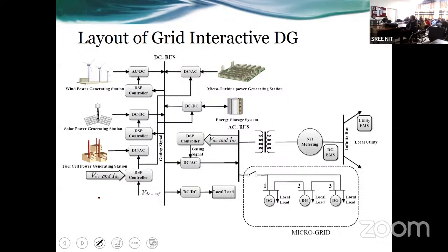So let us say I wish to connect all this power to a 400 V AC supply. My DC bus must be at least twice the RMS voltage. So 400 means you can have almost 760 to 800 V DC link voltage. For that DC link voltage, you have to convert the variable AC coming from the wind turbine into 800 volt. Similarly, the variable voltage coming from the DC power plant, the solar power plant, has to be converted into DC. So everything needs to be brought onto the DC bus.